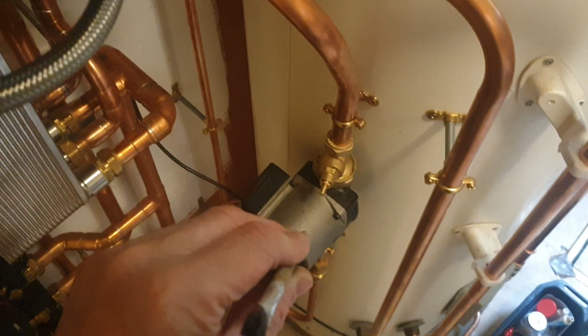is my power - there's a P1 and a P2, and these change function according to what you're doing. So it's a bit complicated here, but basically for external pumps, P1 will drive my secondary circuit pump unless I fit a secondary circulation domestic hot water pump, in which case P2 becomes the one that drives my unmixed circuit pump through my unmixed circuit - not my secondary circulation pump, sorry.